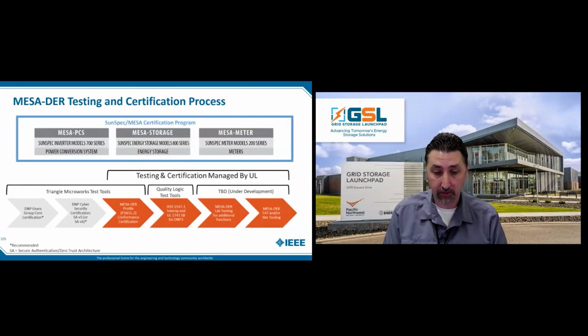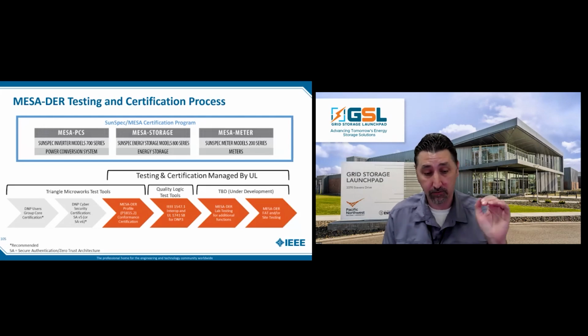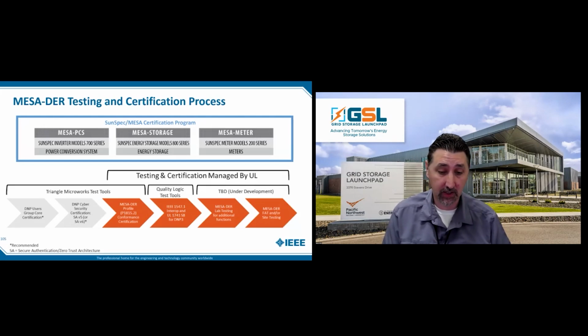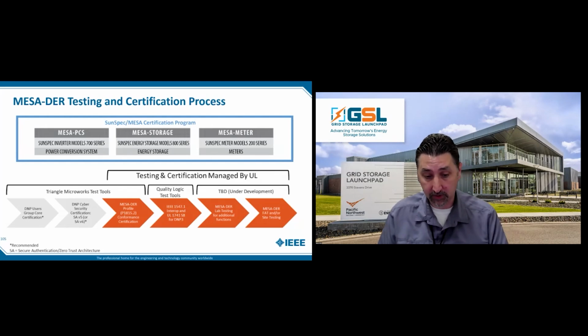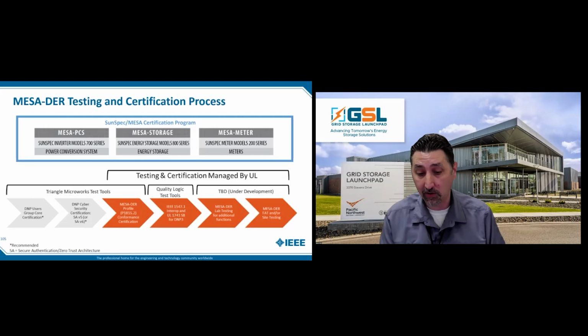So you have other test programs that you want to stack. You do 1547 testing and certification, that gets you part of the way. Then you do the Mesa profile, the communication protocol testing, and that gets you part of the way further - it gets you the communications associated with storage. Then you go out and do lab testing for functionality - they check, using some quality logic test tools in this example, that they're able to meet some of those other functional capabilities. The ones we're working on right now are those functional capabilities for storage.